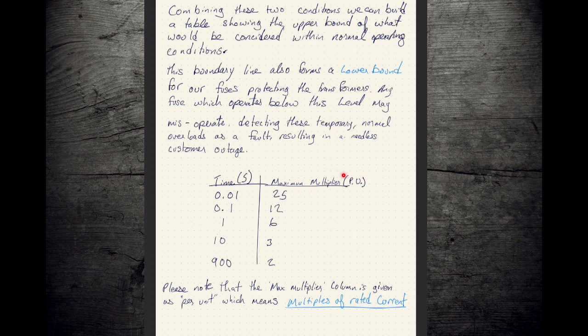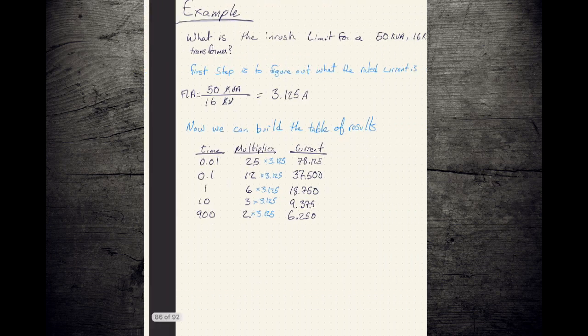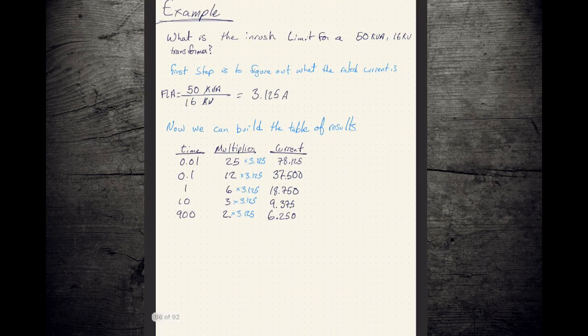So per unit, this is multiples of our full load rating. And so you can see these inrush values, these things are intense. Our fusing has to be permissive enough to allow it, but also our transformers have to be robust enough that they can take these kinds of short-term overloads without being damaged. So let's do an example. For example, what would the inrush limit be for a 50 kVA, very common transformer, fed at 16,000 volts?